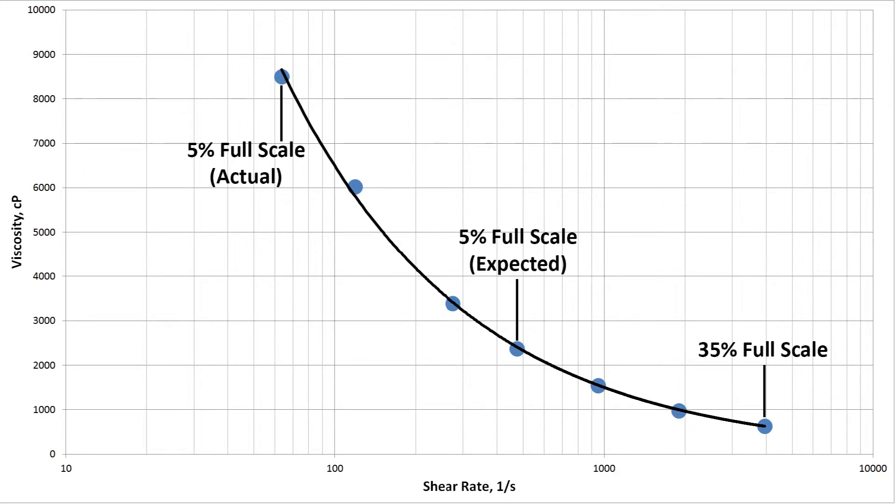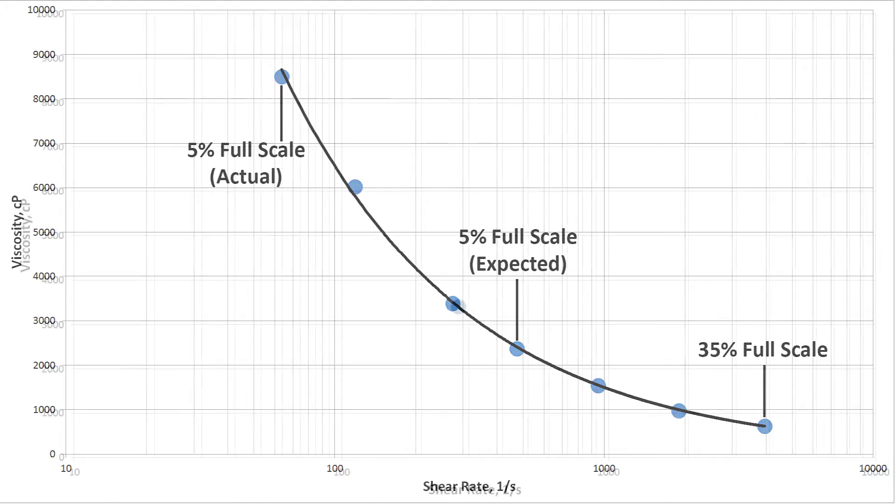If you don't have a full understanding of your sample's shear thinning behavior, the only way to test it across the full range is by trial and error. That is to say, you can keep increasing the shear rate until you truly reach the limits of the chip or instrument.